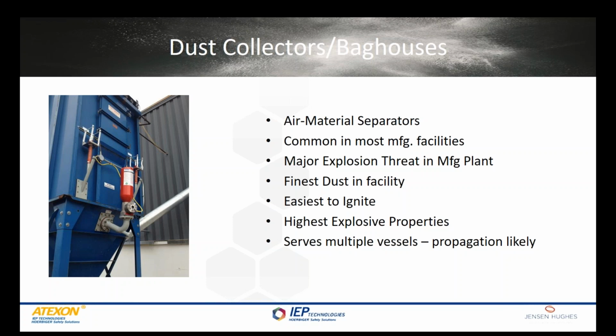One other factor about dust collectors: if you have an explosion in a dust collector, oftentimes that dust collector is serving multiple vessels, so you're pulling dust from multiple sources. A dust collector that has an explosion within it that travels upstream can affect multiple areas of the plant. So you can have multiple explosions within the facility if that explosion has not been isolated.